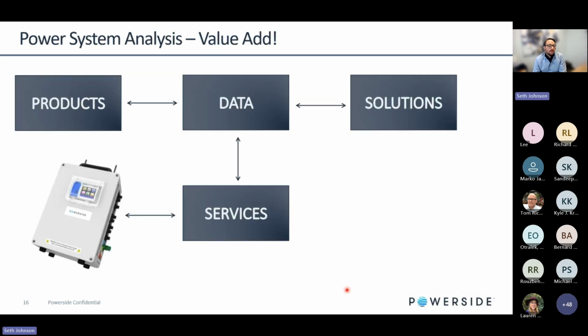So one of the things that customers come to us for is they know us because of our products, both low and medium voltage, and I like to say this is our business process here. A lot of clients come to us and say, hey, we need a capacitor bank, or we need an active filter, or we need a medium voltage product. But a lot of times we need more data to determine what the client actually needs. In a lot of brownfield applications, you'll get into facilities and you'll see equipment that's failed. Certainly, every piece of electrical equipment has a lifespan, but it's good to understand whether or not there's been a misapplication of the existing equipment that's been installed.